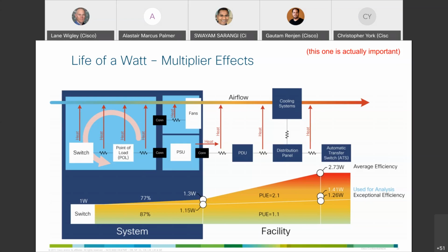In this case, those point-of-loads generate heat, so that's power that's been lost. Going over the backplane or fabric, that's lost too. The fans have to generate a little of their own heat, and power supplies generate heat. Now getting outside the rack, we've got power cables losing some heat. The PDU takes power from the facility and makes it ready for the router, doing things like voltage conversion and cleaning up the power. All these things take power, and the cooling systems take lots of power, switches, et cetera. So there's a cumulative effect of every watt the ASIC takes, quite a bit more power in the system.